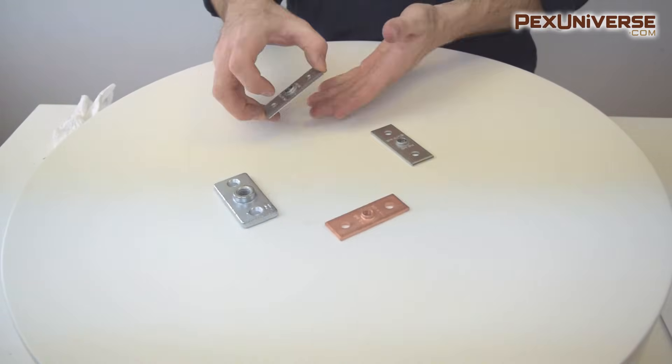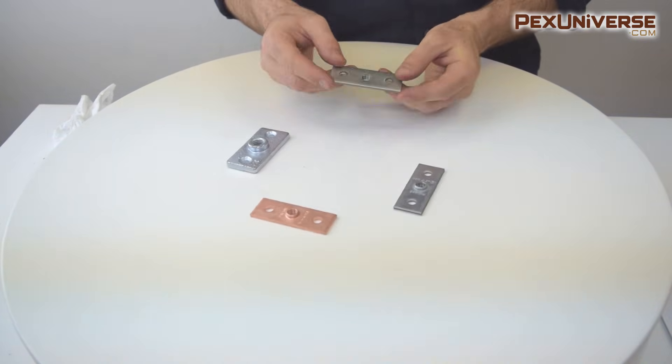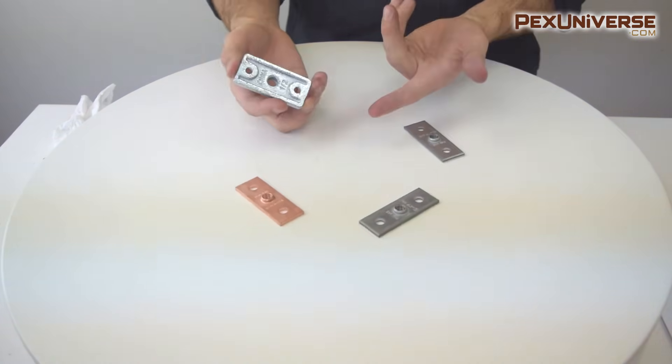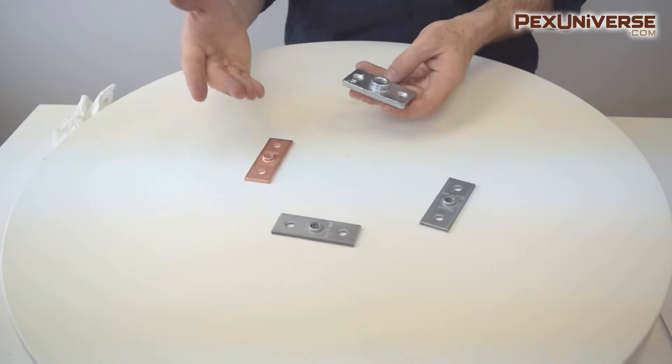Ceiling flanges are designed to provide means for attaching a hanger rod to wooden beams or ceilings. The maximum recommended load for this model of flange is 180 pounds, but it varies as you get larger ones.